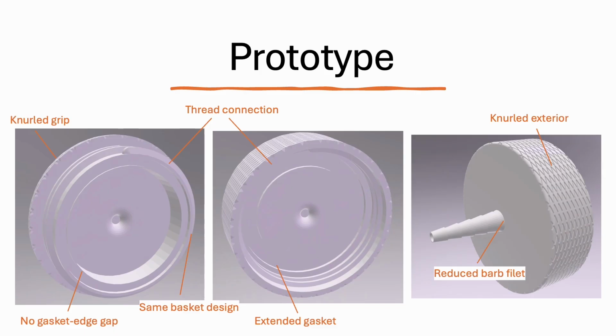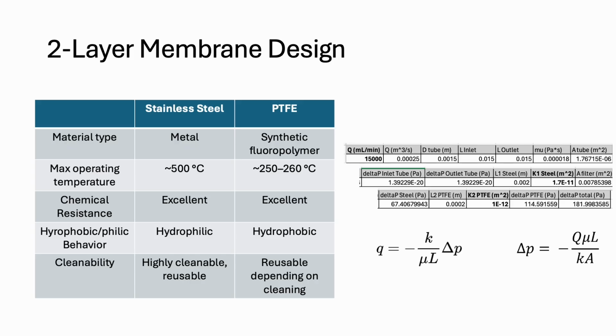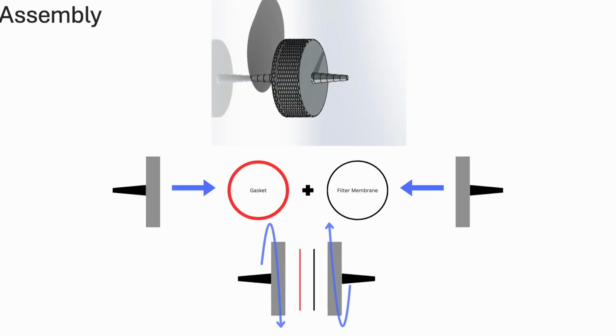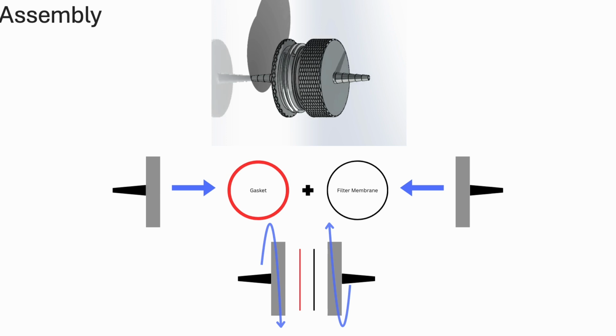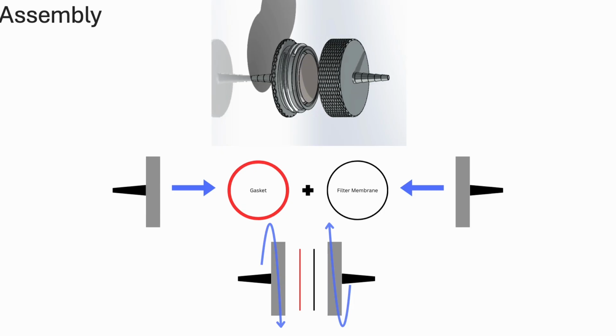So here's what we did. We designed our prototype with easy-to-use manufacturing methods, making sure it can be produced locally in areas that don't have a ton of resources. The housing is built from a tough, sterilizable plastic, and both mesh layers are super easy to swap out. Basically, we wanted everything to keep clinicians safe while still feeling familiar, user-friendly, and most importantly, reusable. You can also see we added a textured exterior on the housing to give the user a better grip. Plus, we used a 2-part threaded design that improves how well it seals and how many times you can reuse it. There's also a gasket between the housing and the filter to make sure the vacuum pump works efficiently. And finally, there's a basket that holds our unique 2-layer mesh filter, which is designed to last longer.